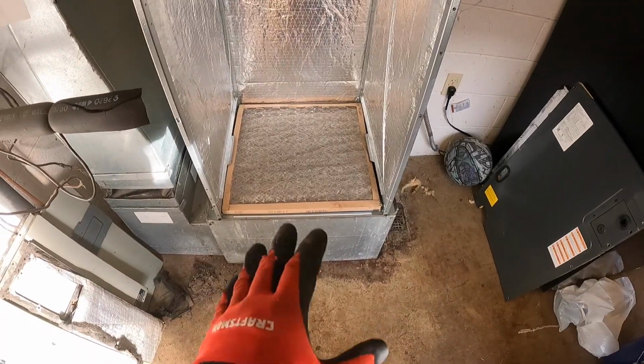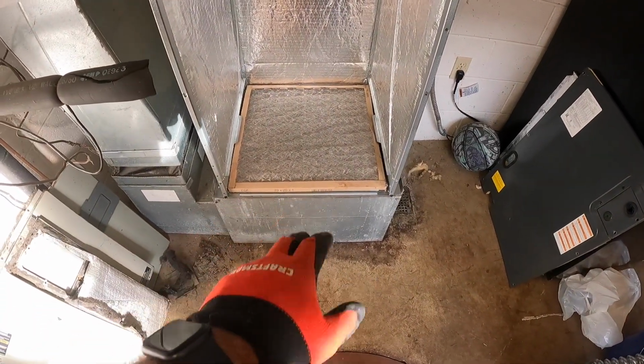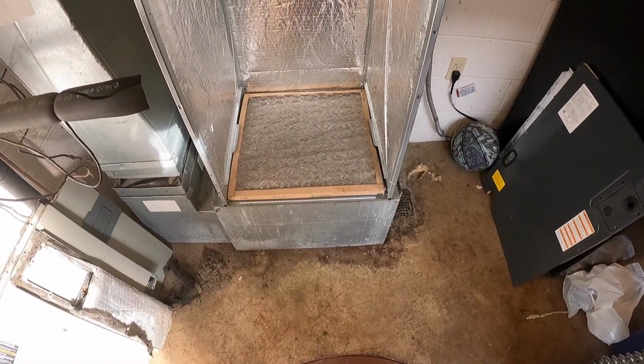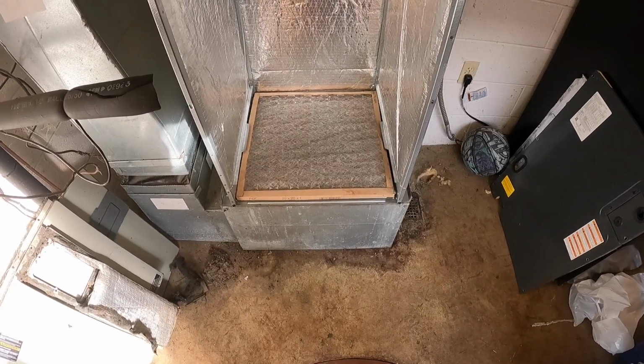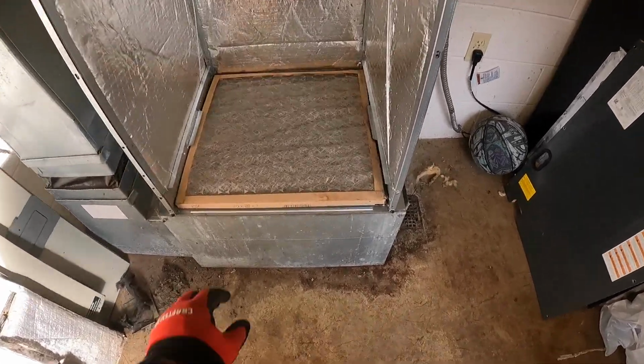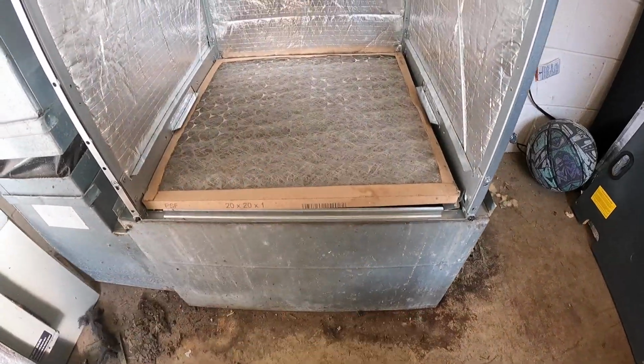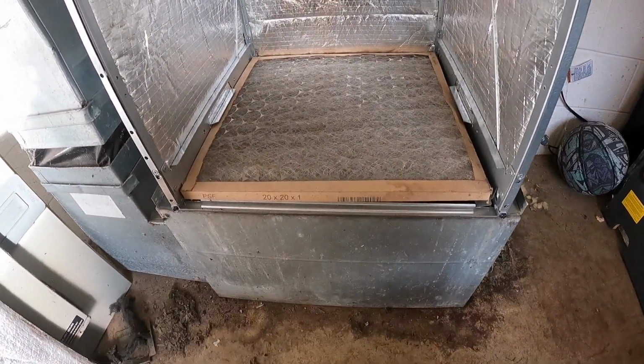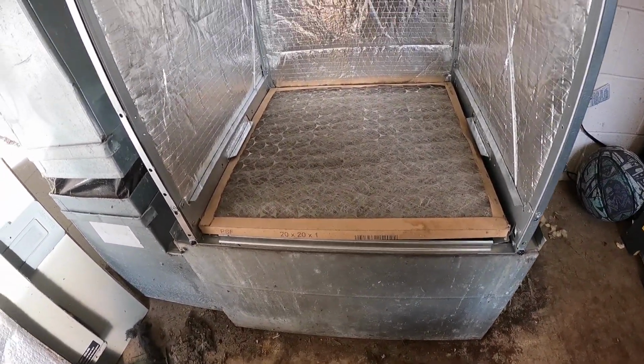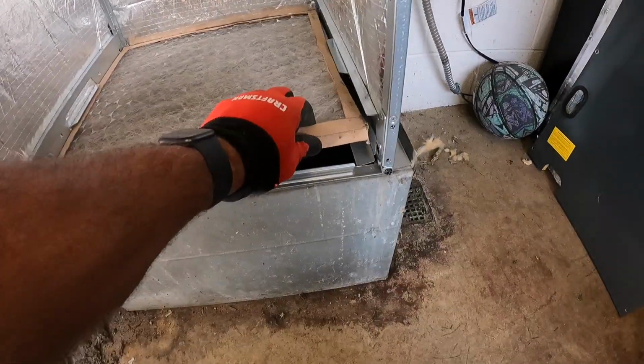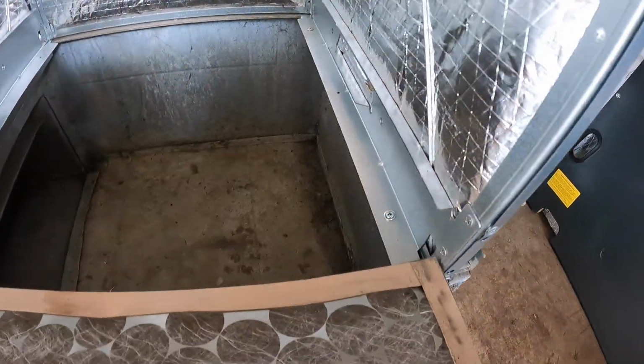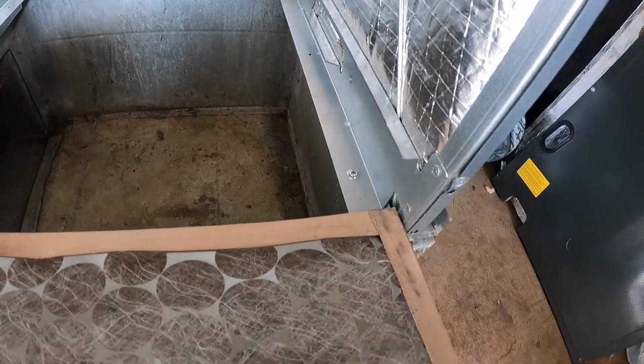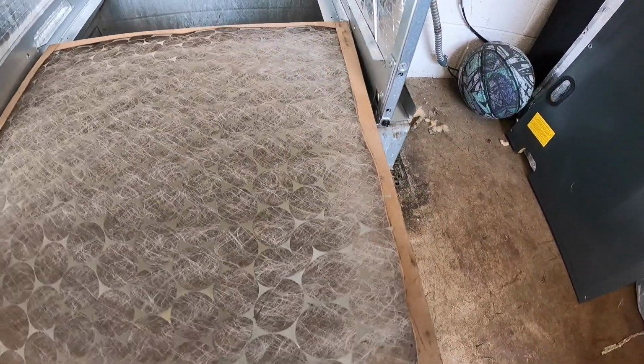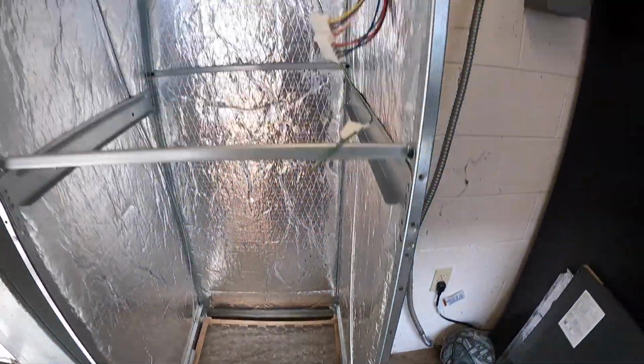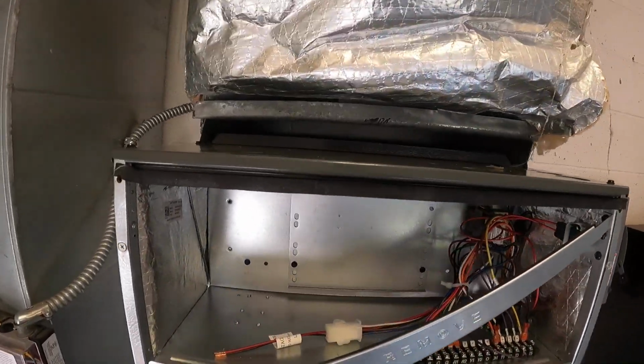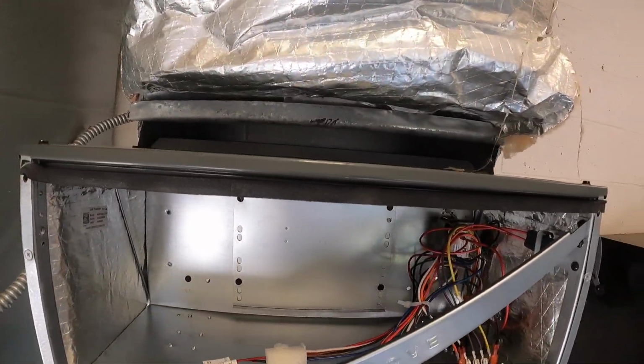Got her sitting in there. I was checking that old filter to make sure it fit — the Goodman paperwork said 19.5 by 20, but these fit just fine. I'll get with the custodian when I see him and have him bring a new one out to put in there. I've got it screwed down on the bottom with some tech screws; the heads won't really affect the filter as it slides over them. You can see how I bent that up to give me room to slide those flanges back in.